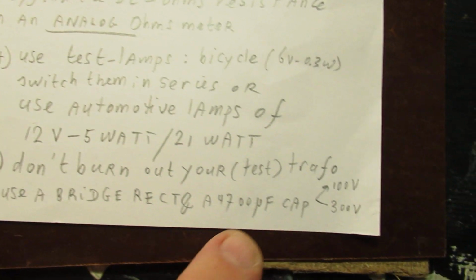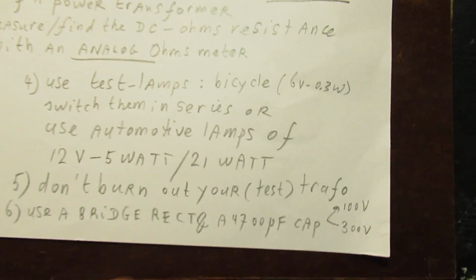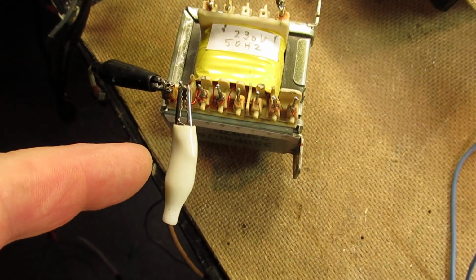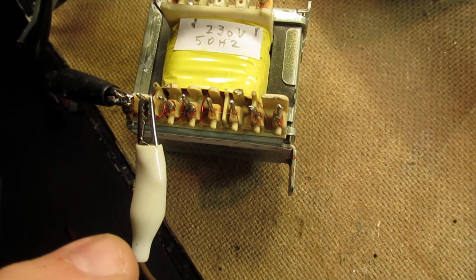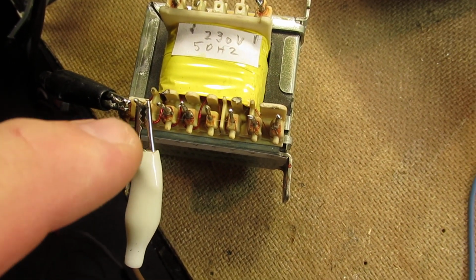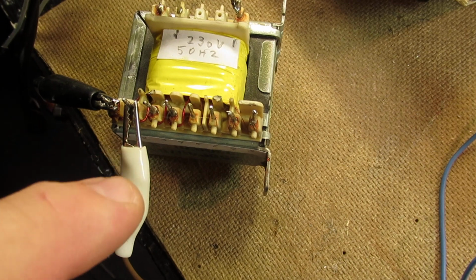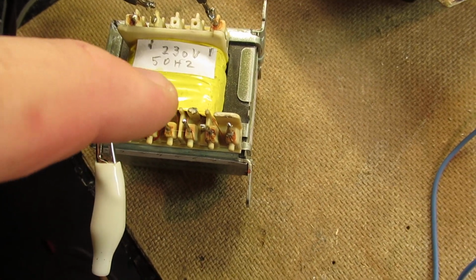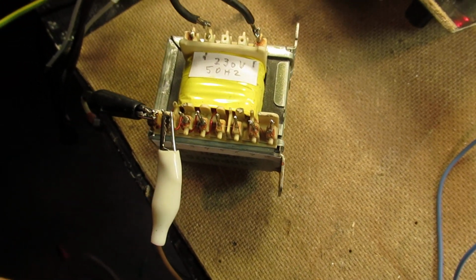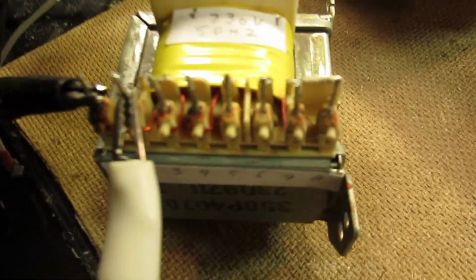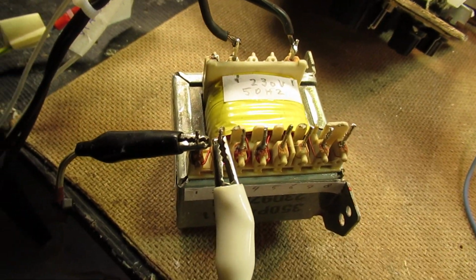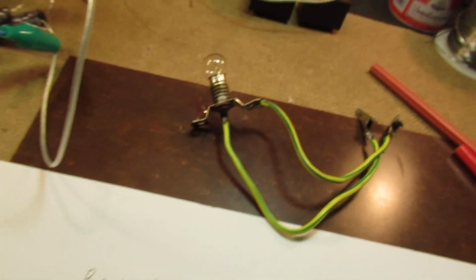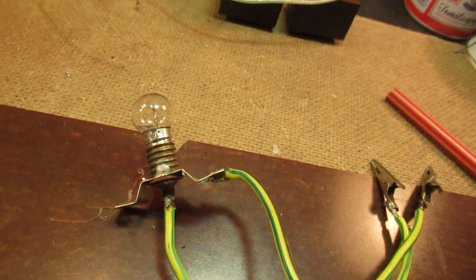Good advice: don't burn out your test transformer. So don't connect on the secondary, especially the secondary, a too low resistance. That will cause the secondary winding to burn out. So when you want to be very careful, start with a bicycle lamp.